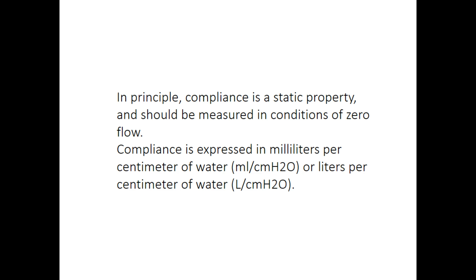If we measure the internal pressure and balloon volume simultaneously, and then plot the readings on a graph, we get two different pressure volume curves. These two curves have different angles to the horizontal. These different angles show the different levels of compliance of the two balloons. In principle, compliance is a static property, and should be measured in conditions of zero flow. Compliance is expressed in milliliters per centimeter of water or liters per centimeter of water.